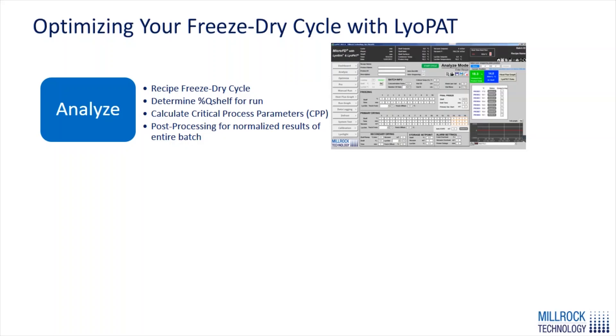When developing or optimizing a freeze drying cycle using the LyoPAT features available in the MicroFD, we recommend starting by analyzing your existing or new cycle by running a plain, recipe-based freeze drying cycle — either based on existing conditions or a more conservative cycle you can safely process your product at. During the cycle, we calculate using the LyoPAT heat flux sensor our critical process parameters throughout the run, and use post-processing to get normalized results accounting for all heat flow in the system.